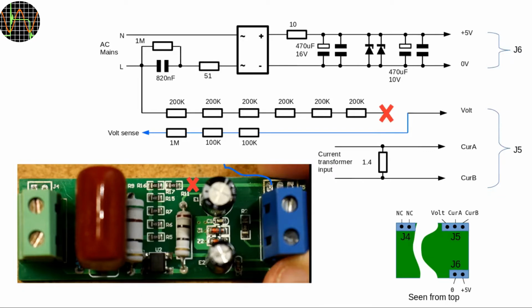With that problem out of the way, it's high time to get to the promised modification. If you recall the schematics of the power board, it is clear that to make this unit measure from 0 volts onwards, we need to disconnect the voltage measuring input from the AC mains input.